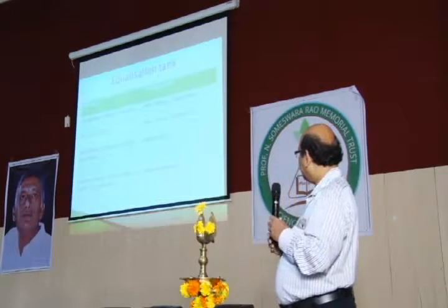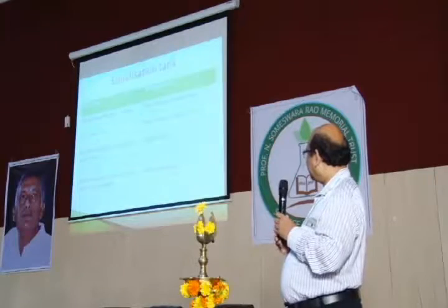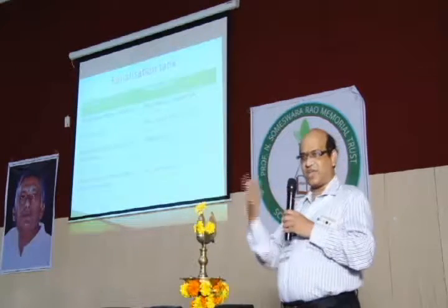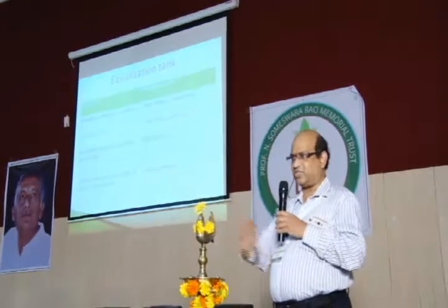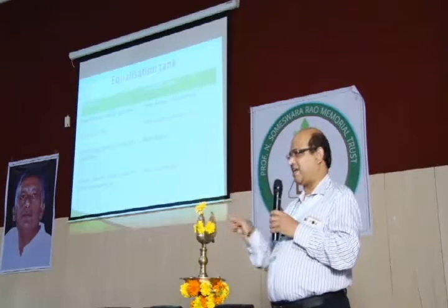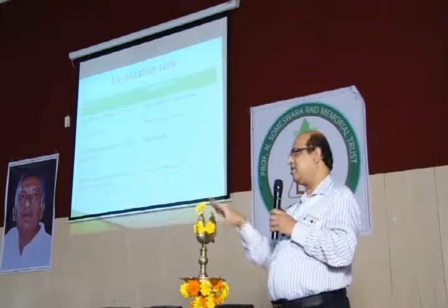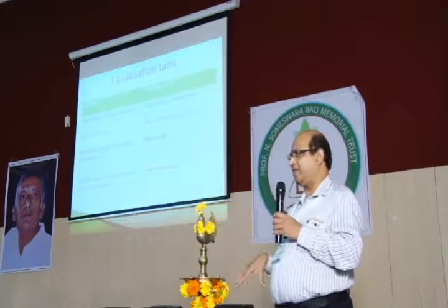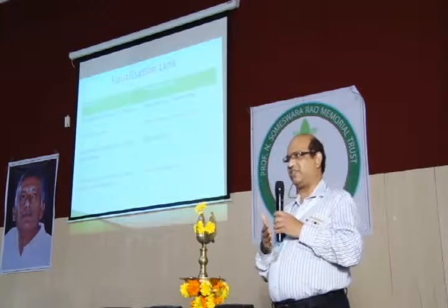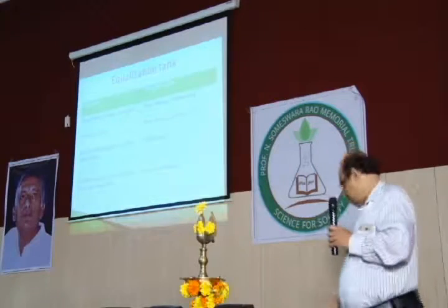Sometimes peak flows cannot be taken out, and sometimes solid accumulation is there. So the equalization tank should have an agitator also, so that nothing can settle. Our only purpose is to have a uniform flow over 24 hours. It should not be very concentrated, and it should not be dynamic.